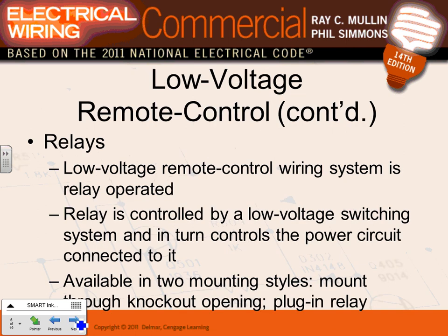Okay, remote control relays. So the heart of the lighting control panel is a relay, guys. Something called a relay. That's the heart of the control panel. That's the liaison between the power system and the low voltage system. You're going to see in a second how the low voltage remote system is relay operated. These relays can be electronic relays, or they can be electromagnetic: coil energized, shut. Or they get a signal, close the contact, make that transistor close.